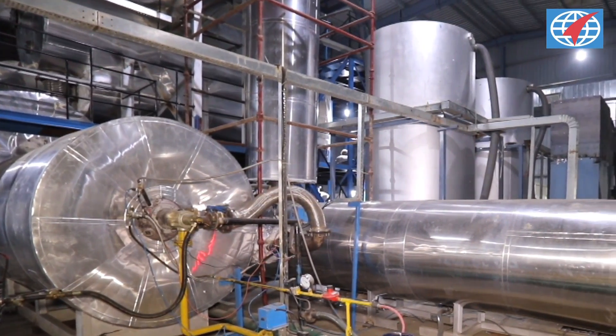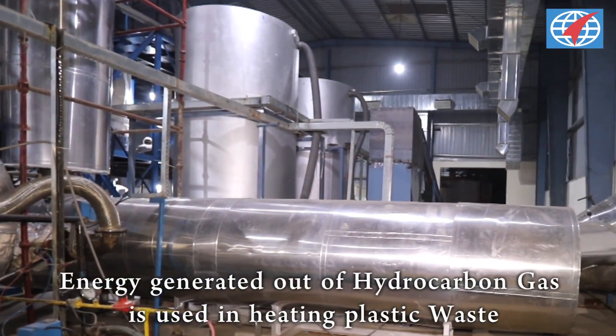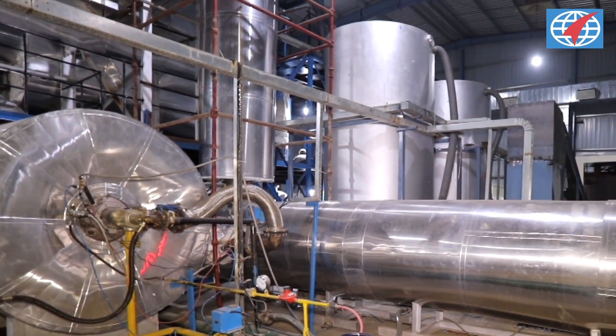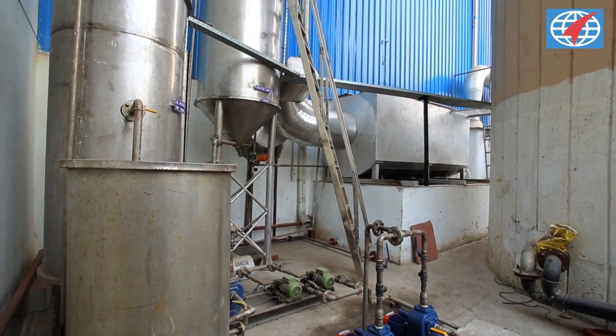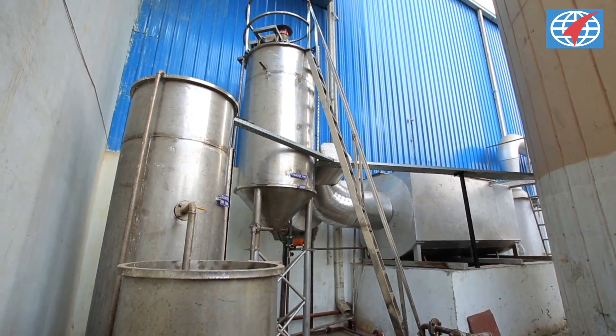Hydrocarbon gas is used in the pyrolysis hot air generator, and the energy generated is fed back to the pyrolysis reactor for heating the plastic waste. The exhaust gases are fed to the air preheater to gain combustion air temperature and further used in the evaporator to vaporize the dirty water generated by the effluent treatment plant.